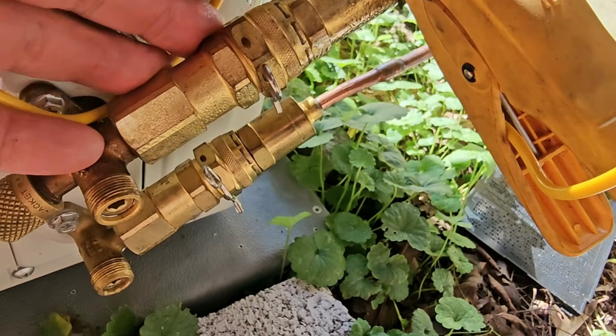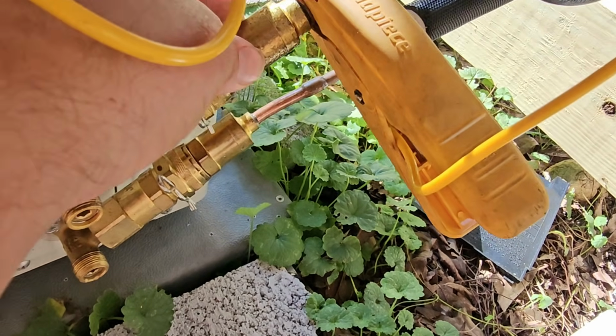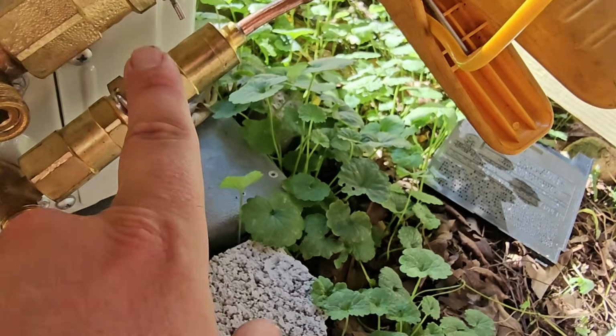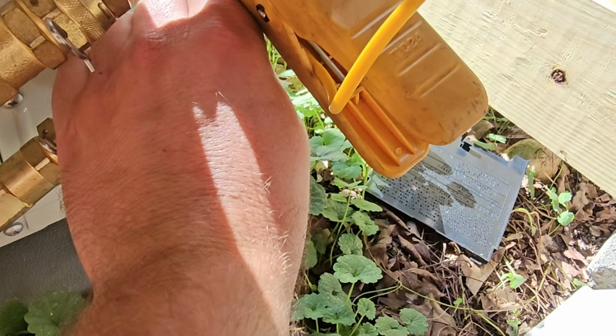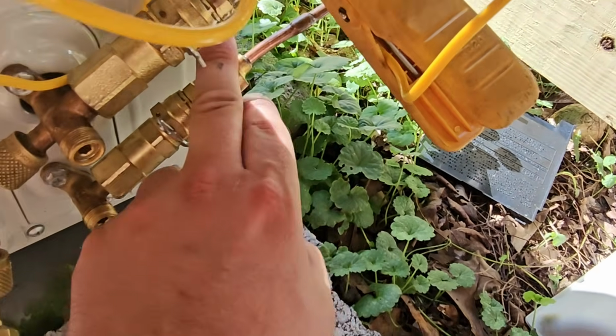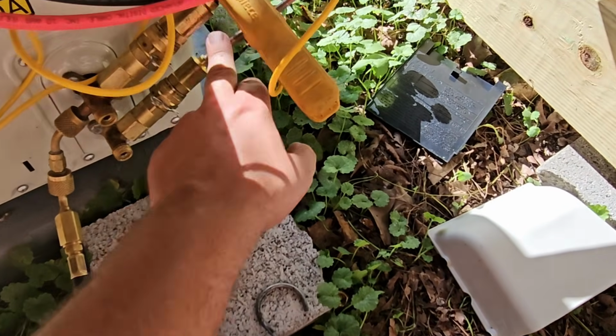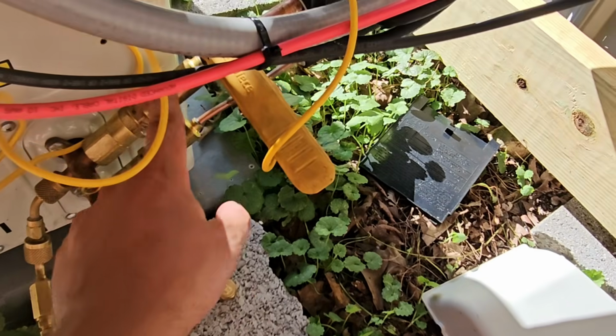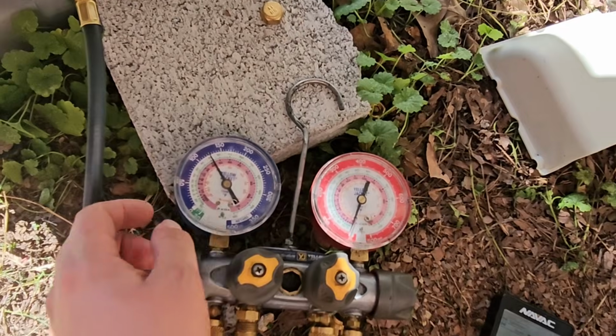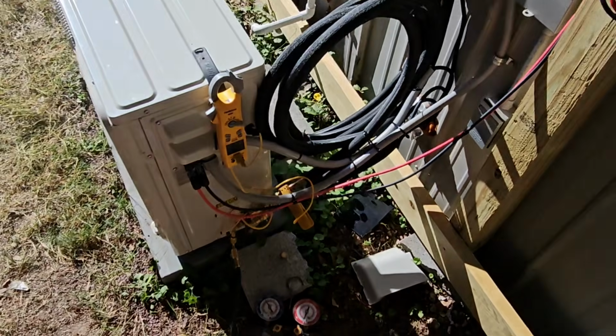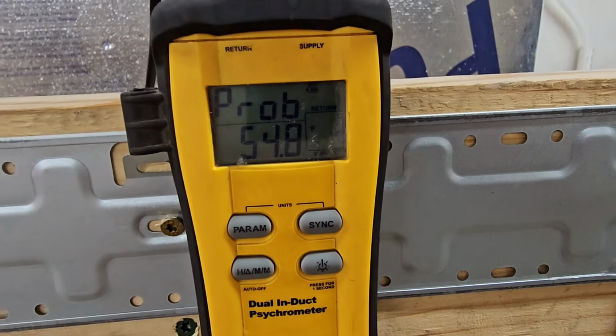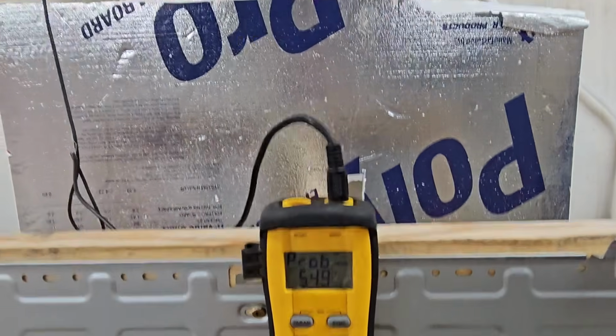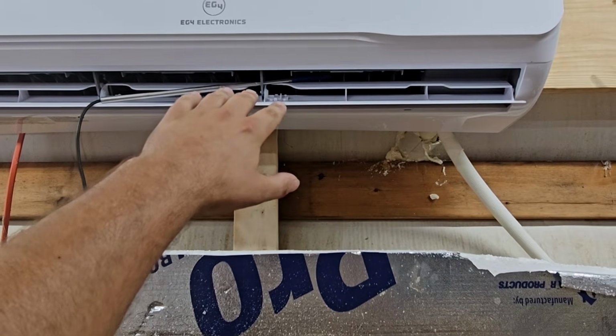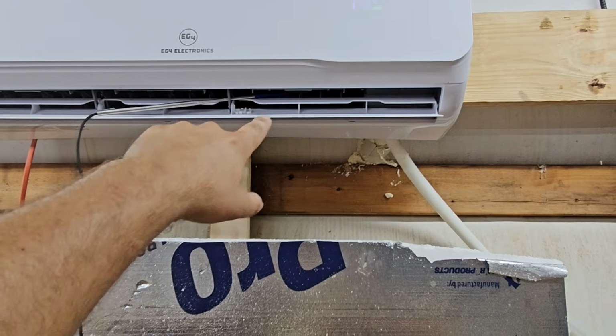Now our suction line is nice and cold. Before it wasn't this cold, it was warmer. Our liquid line, it's warmer. It's not ice cold like it was. This should never be iced over. This right here should be nice and chilly. So now let's check our supply air temperature. Supply air temperature is 54 degrees now. That is much better. That is nice.